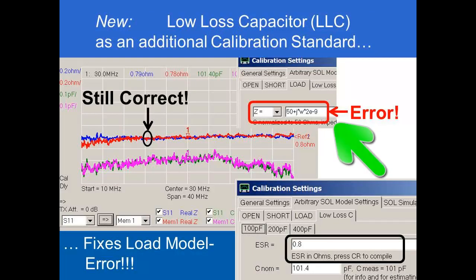The rescue is a new calibration method, invented by Hewlett-Packard long ago, but new to me. It is possible to repair this model error by introducing a new additional calibration standard, for example, a capacitor. The only condition is that the equivalent series resistance, ESR, of the capacitor standard must be known. If the ESR is 0, then the method works best possible, as no error can occur, so the Q of the capacitor used must be very high.